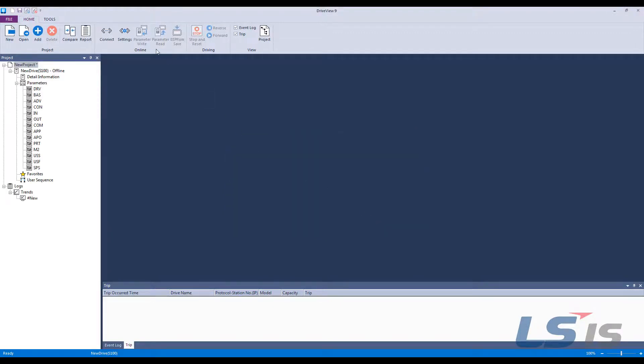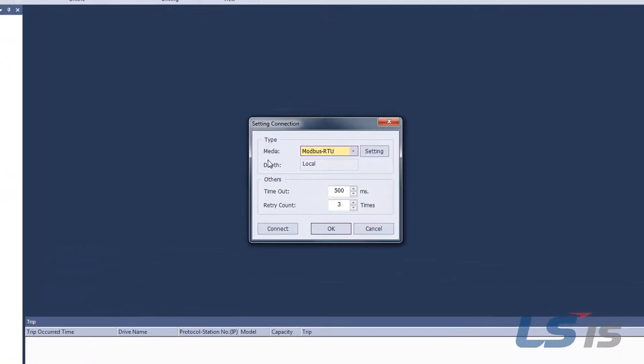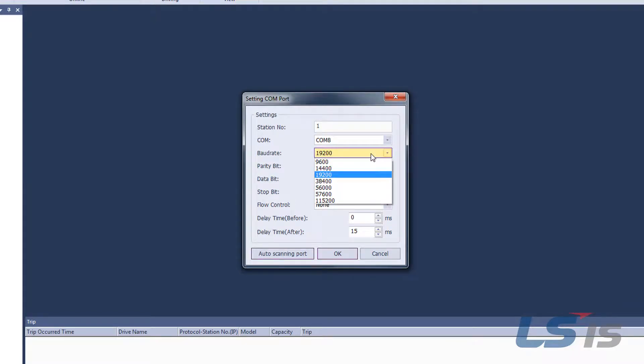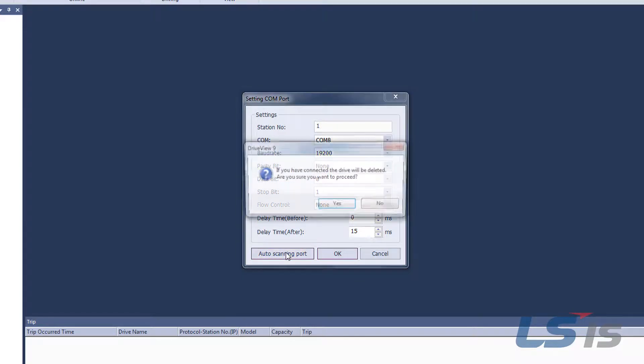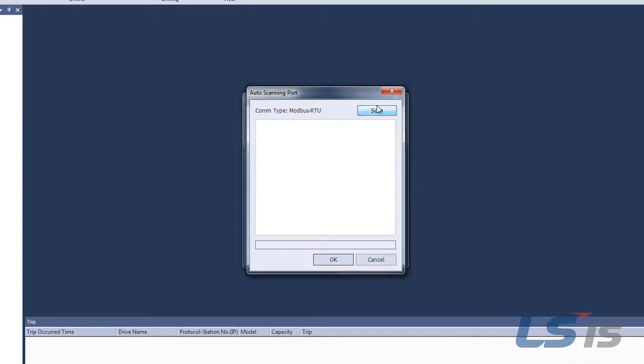Then click settings and confirm that the media is Modbus RTU. Select setting, change the baud rate to 19.2, and select auto scanning port and scan.